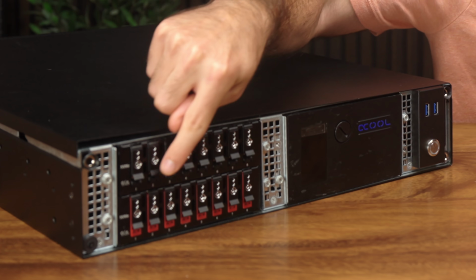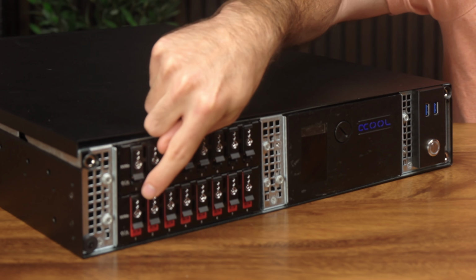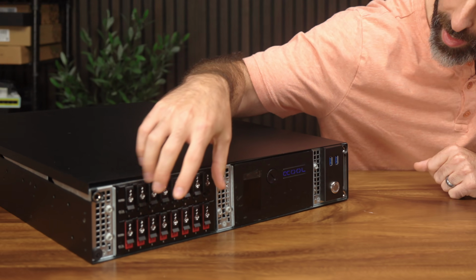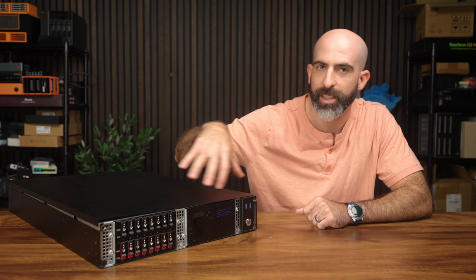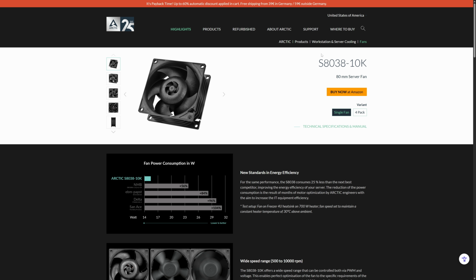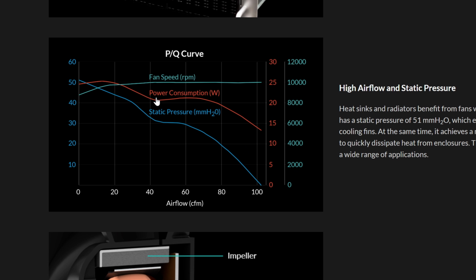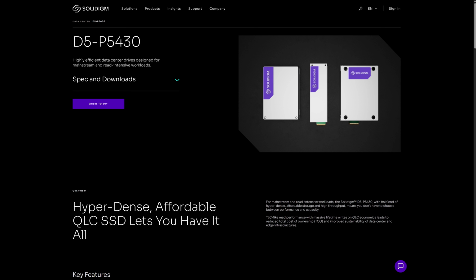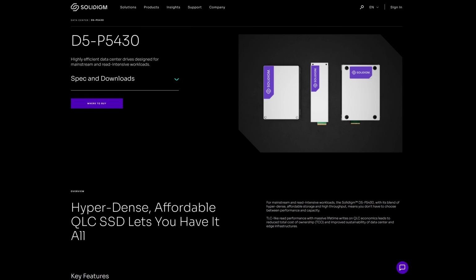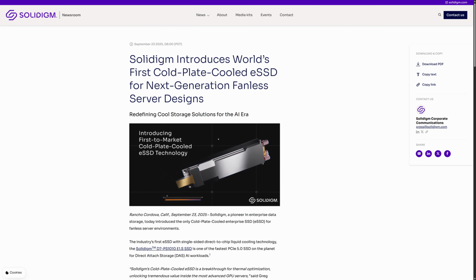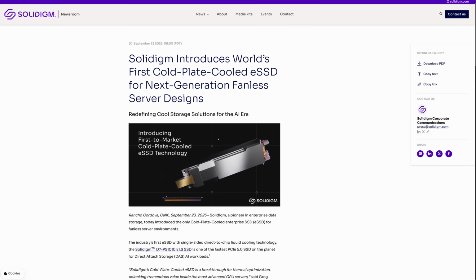Look how dense we have these drives together—that's 8 E1.S drives in like a quarter of this entire area. That's nuts. Usually you'd need super loud fans pulling like 20 watts each, and you still wouldn't see temperatures this good. Also, something to note is that these are just their regular old E1.S drives, not even their purpose-built cold plate drives designed for liquid cooling.